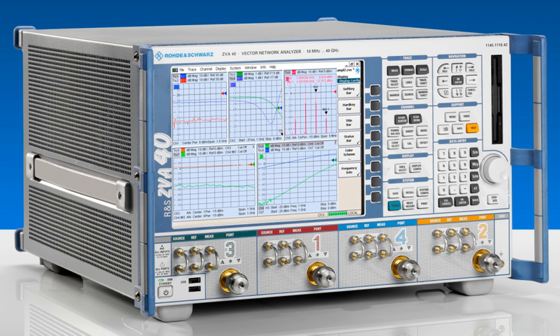For two ports, there are 12 possible systematic errors analogous to the three above. The most common method for correcting for these involves measuring a short, load and open standard on each of the two ports, as well as transmission between the two ports. It is impossible to make a perfect short circuit, as there will always be some inductance in the short. It is impossible to make a perfect open circuit, as there will always be some fringing capacitance.